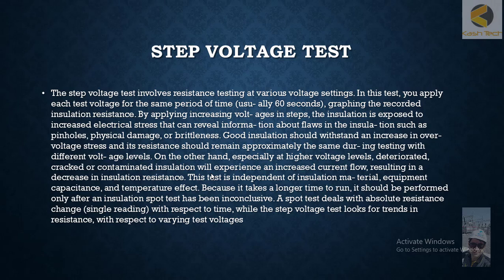Let's discuss a new type of testing method to test insulation resistance, called the step voltage testing method. In this method, step voltage tests involve resistance testing at various voltage settings. We apply 500 volts and take the insulation resistance, then apply 1 kV, then 2 kV, and so on. This is also part of maintenance testing. Each test voltage is applied for the same period of time, for example 60 seconds, graphing the recorded insulation resistance by applying increasing voltages in steps.